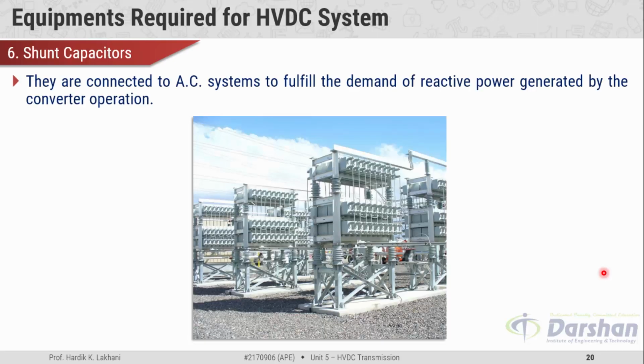Thereafter, shunt capacitors. They are connected to AC systems to fulfill the demand of reactive power generated by the converter operations. So these shunt capacitors are present at the sending end side as well as the receiving end side. They are normally connected to the AC bus on both sides, which means the rectifier at the sending end side and the inverter at the receiving end side.